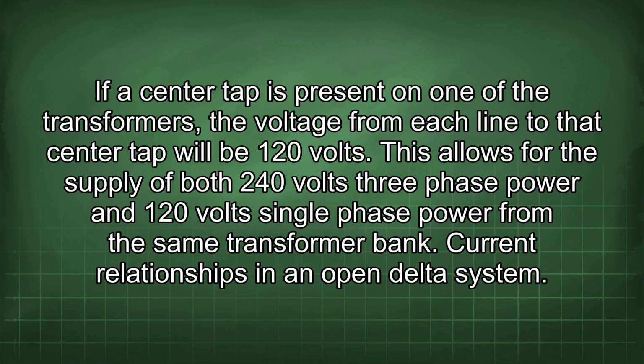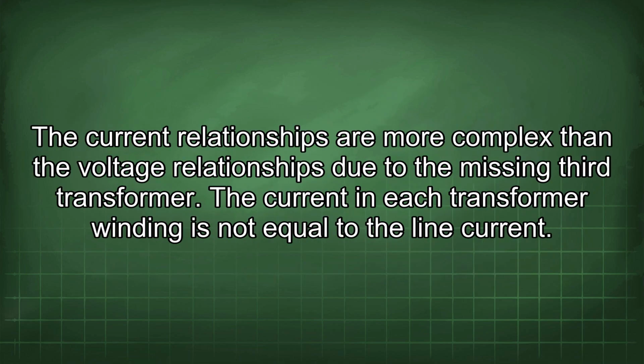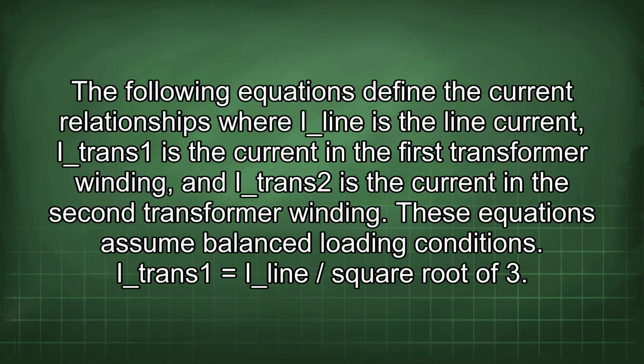Current relationships in an open delta system. The current relationships are more complex than the voltage relationships due to the missing third transformer. The current in each transformer winding is not equal to the line current. The following equations define the current relationships where I line is the line current, I trans1 is the current in the first transformer winding, and I trans2 is the current in the second transformer winding. These equations assume balanced loading conditions.